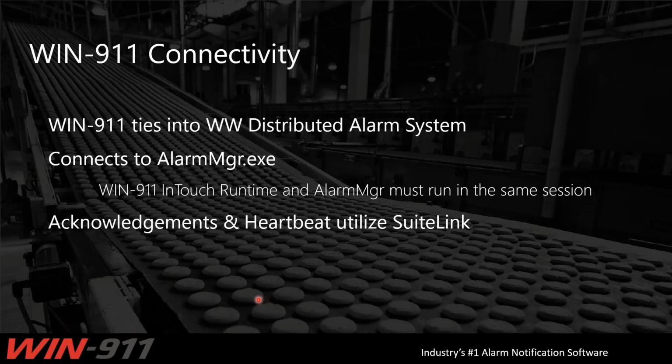Now both our InTouch Runtime, the Win911 InTouch Runtime, and the alarm MGR must run in the same session ID. And what that means is session IDs is like the user interface or the user process for it. Session 0 is typically your console session, a background session like a service. And then session 1 is normally your user interactive service or your session. And so you run Window Maker and as an application that would spawn in session 1.